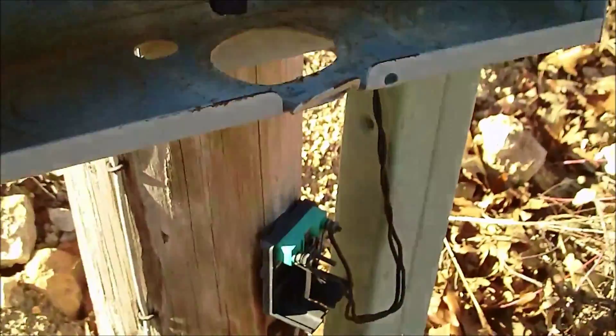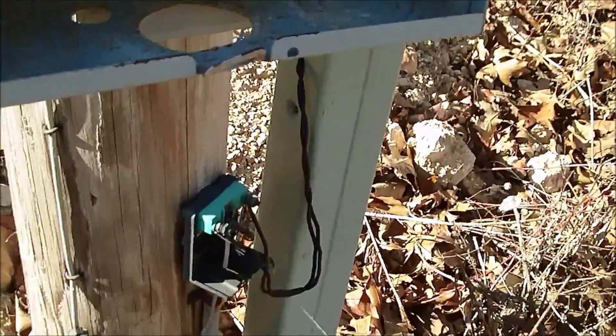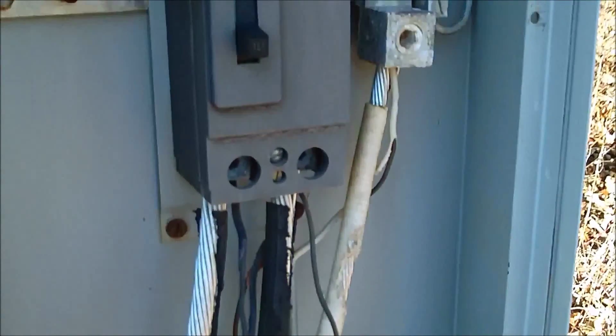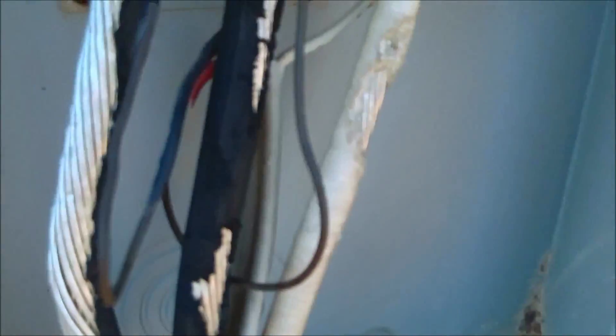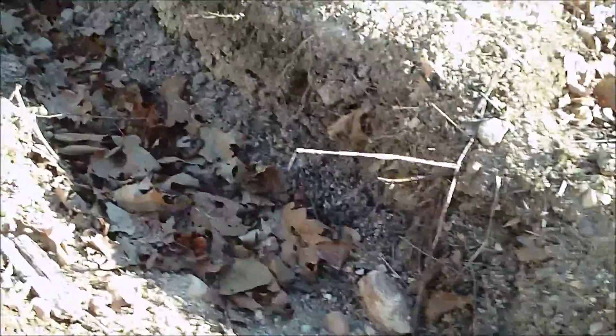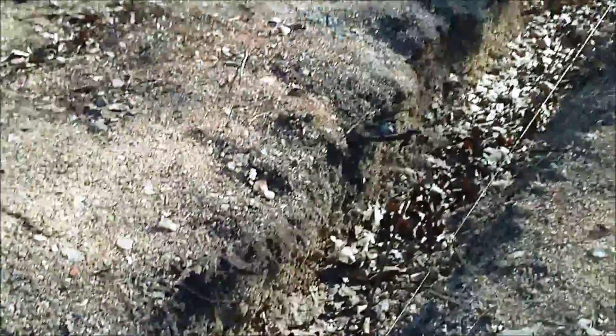The telephone service is right there, but all that will probably have to be updated, because like I said, nobody's lived here in over 25 years. So what I'll do is I'll come in with new wire and put conduit right there down into the ground — I don't know why there isn't already some there, but there's not. I'll run my three wires down the conduit over into my trench here and then run all three wires through the foundation.